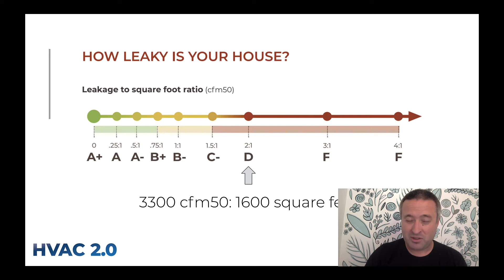But this house is 3,300 CFM 50 to 1,600 square feet, which is right about a 2 to 1. That is a D grade house. And considering that this isn't that old, this house is from the 70s, that's pretty bad. So, and that house is uncontrollable with HVAC alone. Plus, he had 2 systems, which is dumb. A 1,600 square foot house should not have 2 systems. Very uncommon in Cleveland and generally just not a good idea. Here's what the house looks like, a 1,600 square foot split.